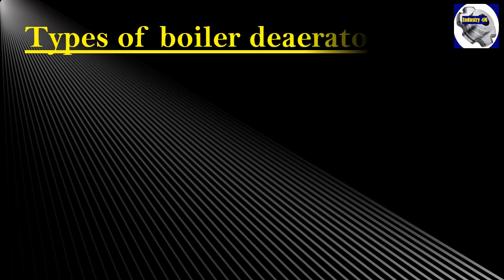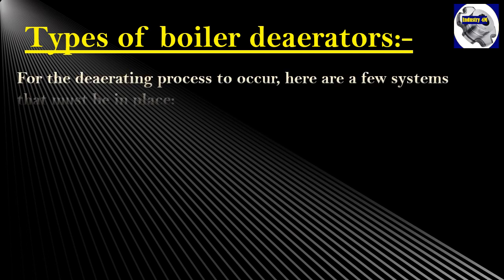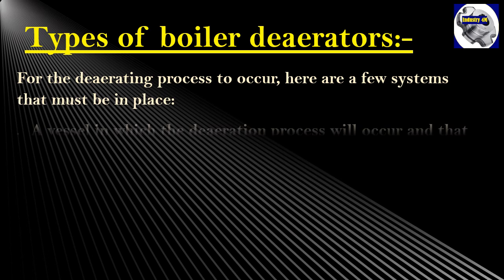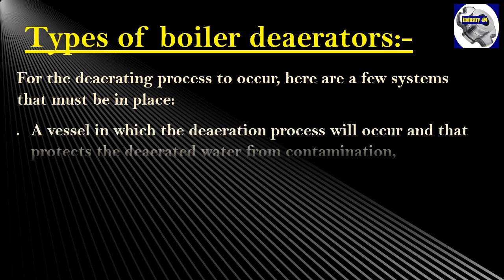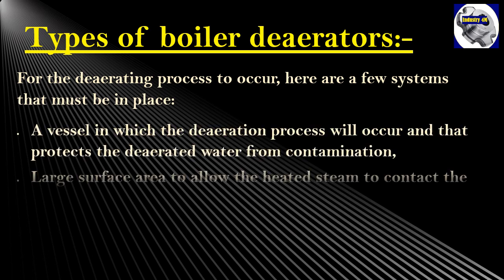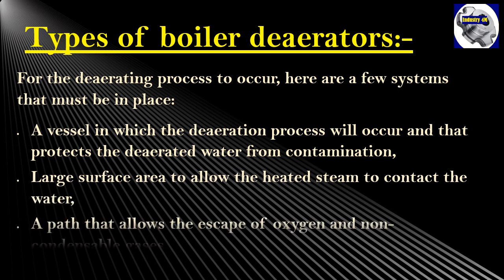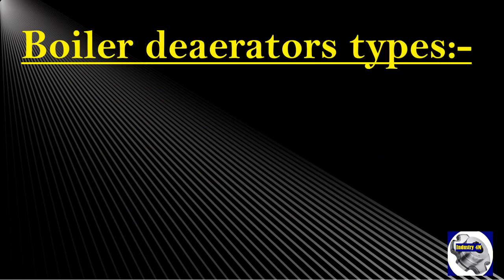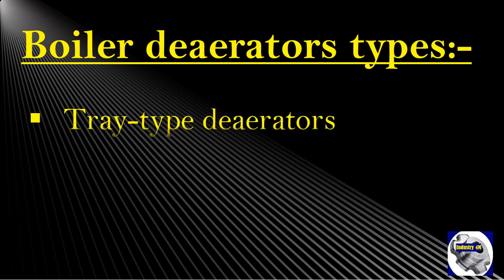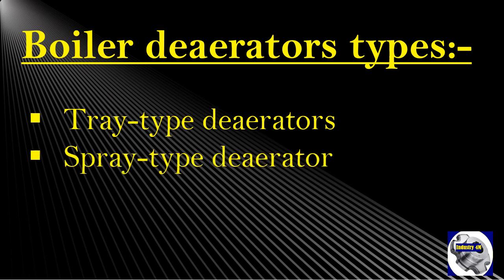For the deaerating process to occur, a few systems must be in place: a vessel in which the deaeration process will occur and that protects the deaerated water from contamination; a large surface area to allow the heated steam to contact the water; and a path that allows the escape of oxygen and non-condensable gases. With that being said, boiler deaerators typically come in two types: tray-type deaerators and spray-type deaerators.